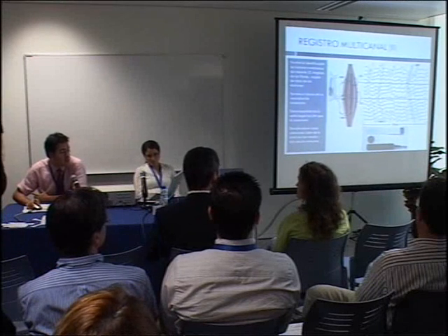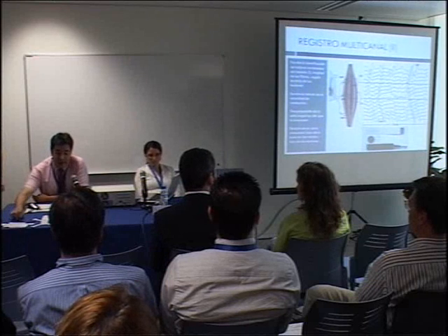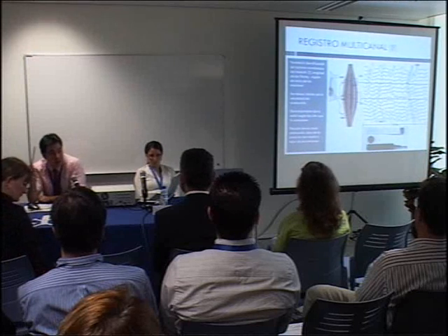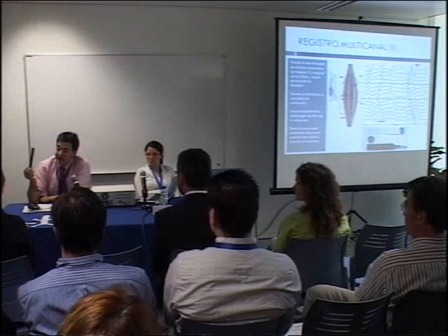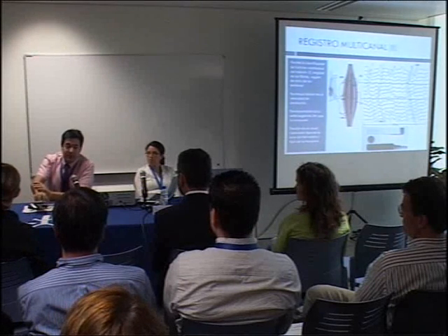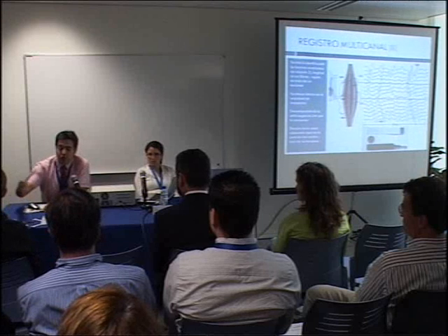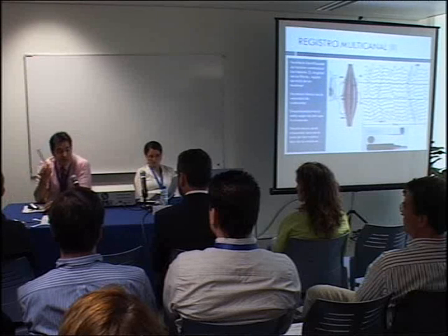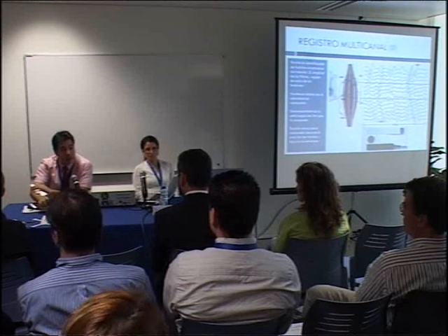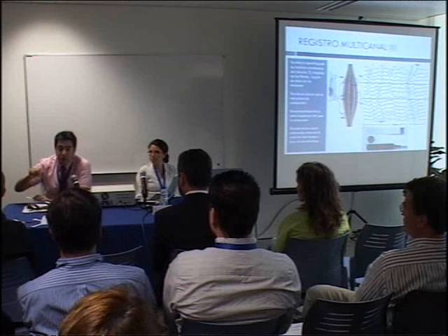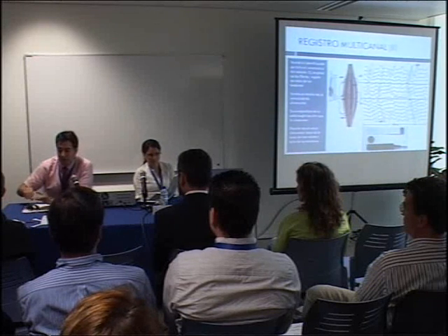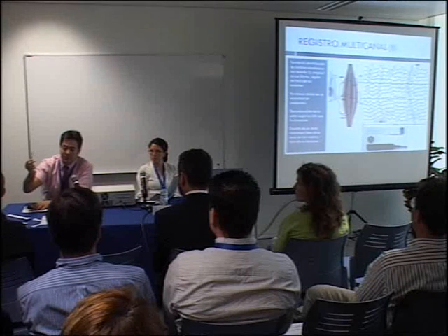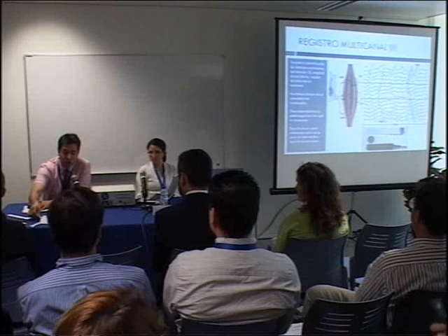Here we have 2 innervation areas. We see the propagation of the signals. The lead matrices being used are linear matrices. These are silver-coated. They permit contact with skin. They can easily be moved about. These are other linear matrices which, by means of adhesive foam, hold better onto the skin or point of interest. When we need to make the recording whilst the muscle is being moved, the signal is very good. These are the matrices which are smaller, depending on the length of the muscles.